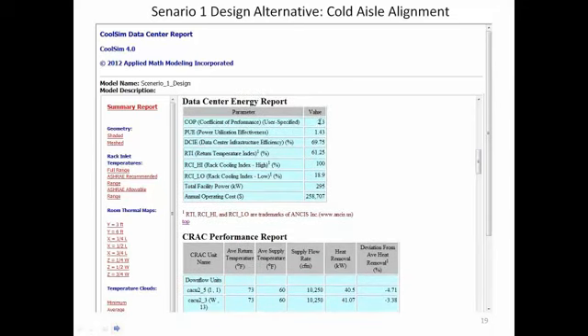Let's see what we've got on the hot side. So if we take a look at the air coming out of the hot side of the racks, this end of the room is the higher density over here, isn't it? Yes. Yeah. And we've got some wrapping up around, a little bit sneaking back in, but for the most part, that's not too bad. So that was option number one, design alternative number one. You showed them some others as well.